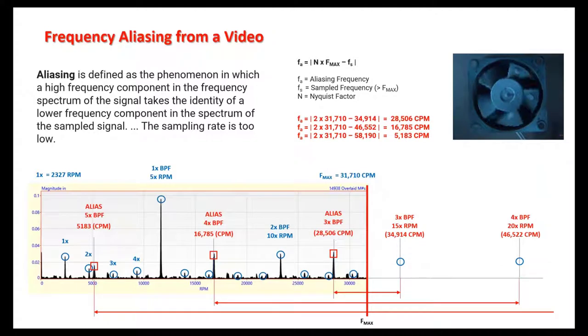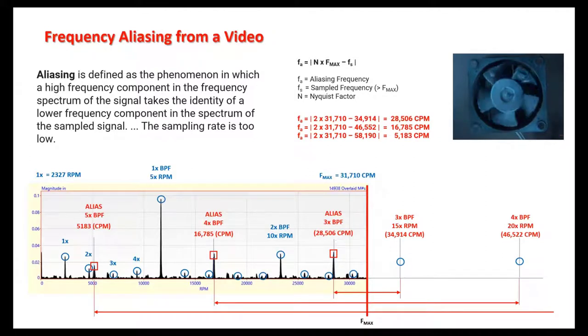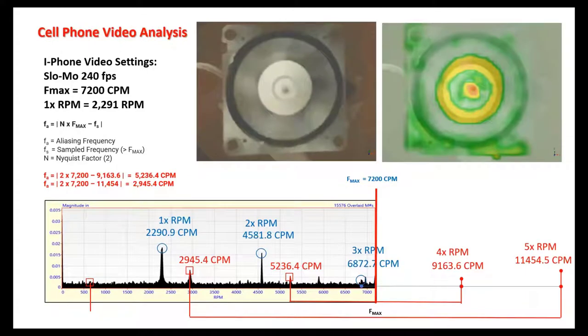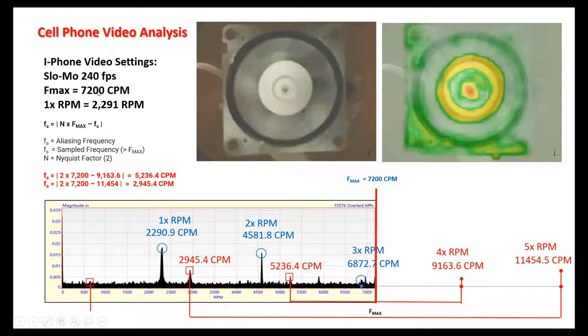If we don't sample fast enough, we can't avoid this problem, and without anti-aliasing filters — which we don't have for digital video — we can't solve it. The best we can do is identify what the alias frequencies are. Now, using the iPhone at slow-motion 240 fps, F-max is 7,200 CPM or 120 Hz. At 2,291 RPM I get two times and three times that running speed, and then I'm done — that's all within F-max.